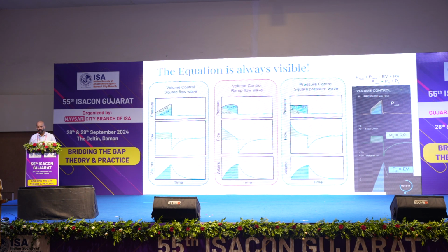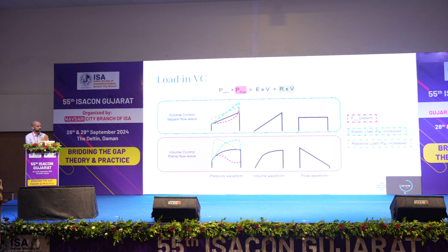So I won't go into details of this because we covered that, but this is where I would like your attention so that you can train your eyes to recognize certain key patterns. You are looking at the load and if you are in volume control, what you will see is that typically the flow waveform will be a square wave.